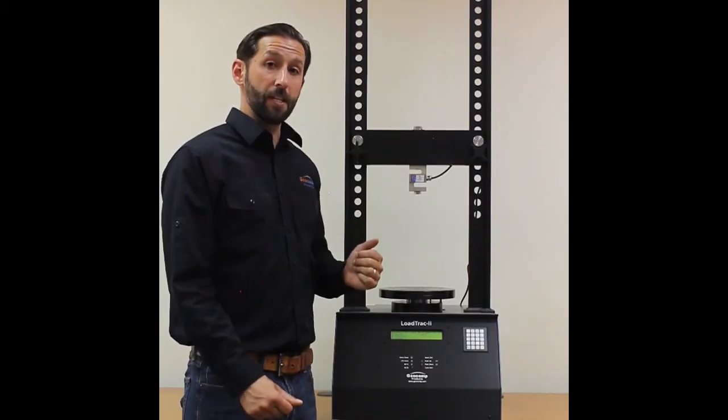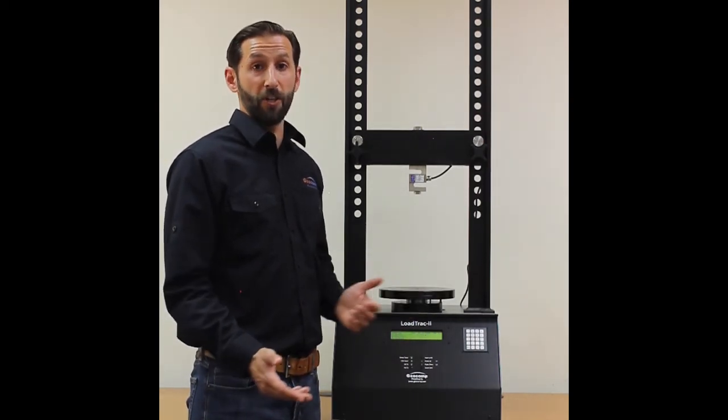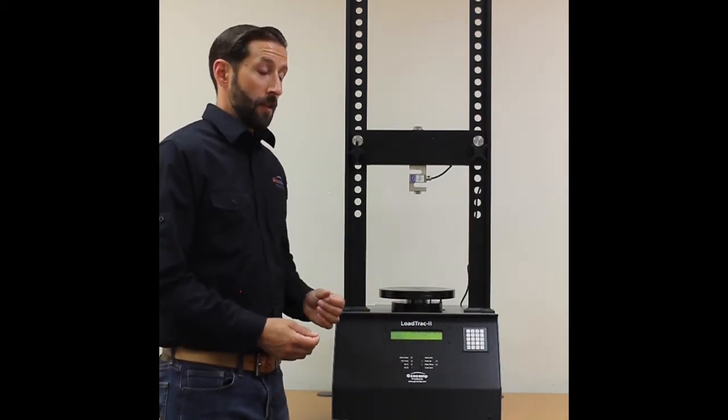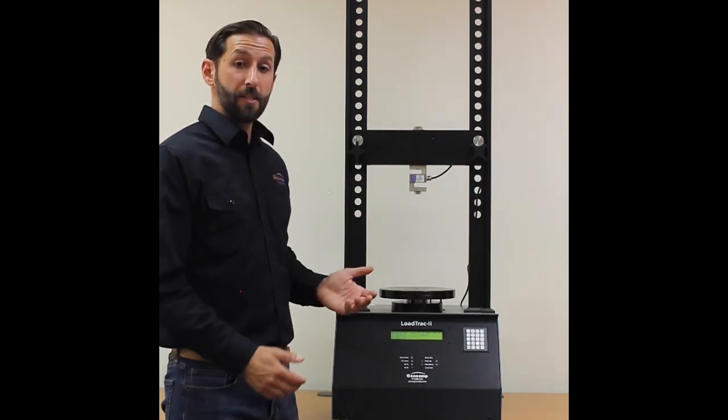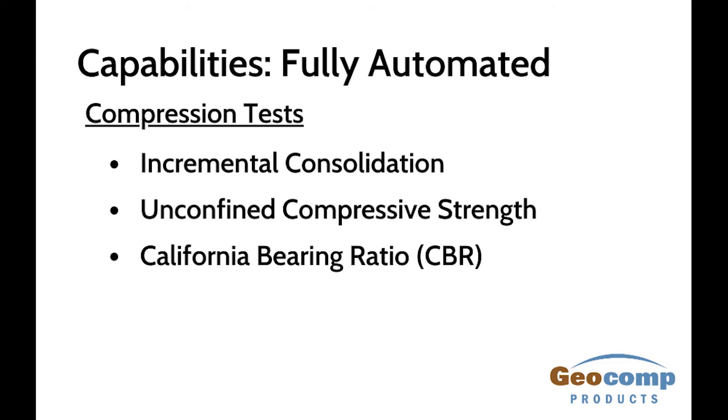Let's talk a little bit about the capabilities of the LoadTrac and why it's such a versatile load frame for your lab. With the proper accessories and software, the LoadTrac 2 can perform fully automated a wide range of compression tests. These might include incremental consolidation, unconfined compressive strength, and California bearing ratio, also known as CBR.